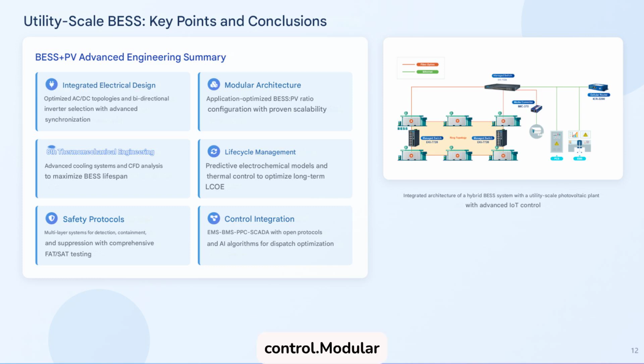Modular architecture: scalability based on racks, containers, and blocks from 1 to 100 megawatt hours. N+1 redundancy and selective maintenance. BESS PV ratios tailored by application: shifting, firm capacity, arbitrage, etc. Modularity equals operational flexibility plus reduced mean time to repair, MTTR.